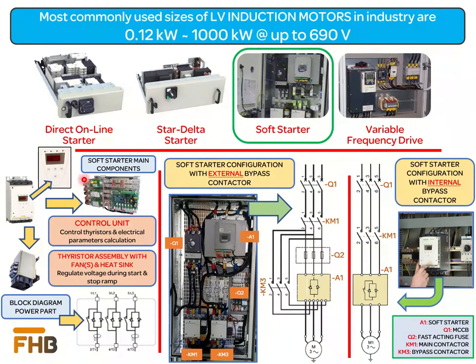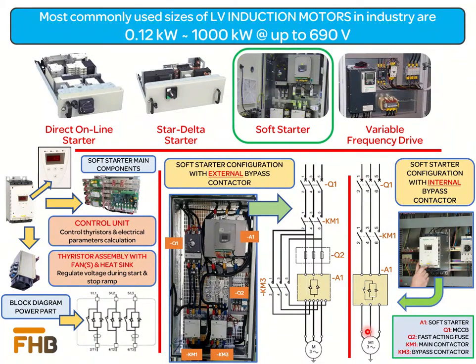The soft starter configuration in power systems for starting an induction motor is developed with either an external or an internal bypass. The main function of the soft starter is to support the starting of the induction motor at the desired current and torque value. Once the motor is started and reaches its full speed, it is unnecessary to continuously pass electrical power through the soft starter's solid state power circuit. The external or internal bypass is used to divert power through an alternate route once the motor is started, reducing heat losses in the solid state section. In case of an external bypass, a separate power contactor is used. Some soft starters are designed with an internal bypass contact, in which case no external bypass contactor is required.